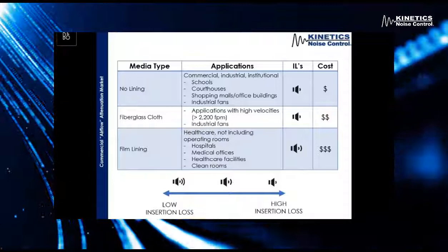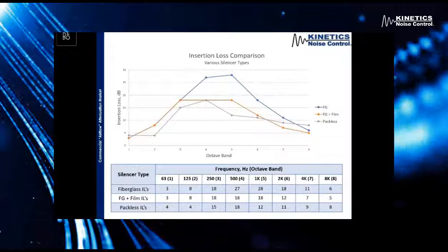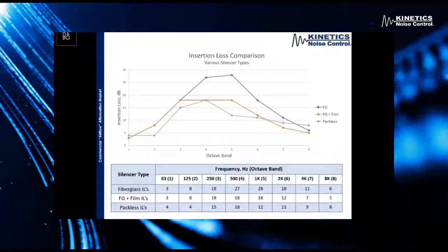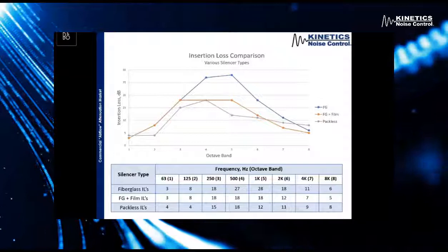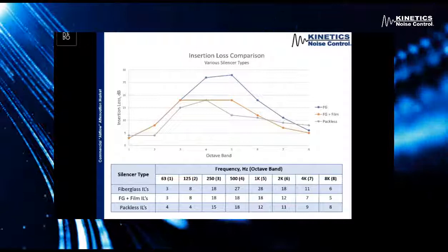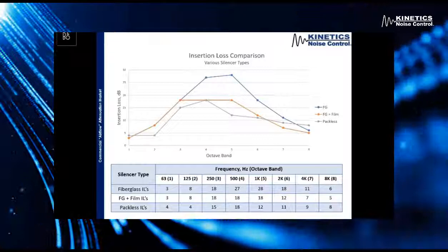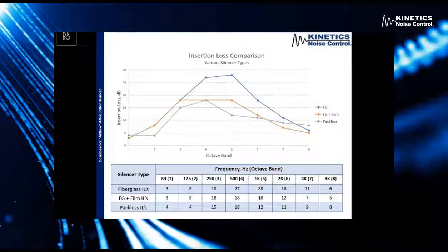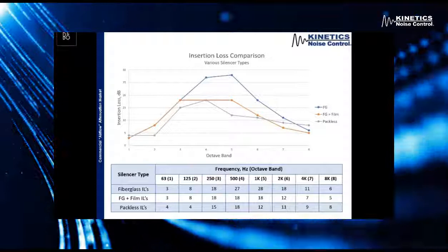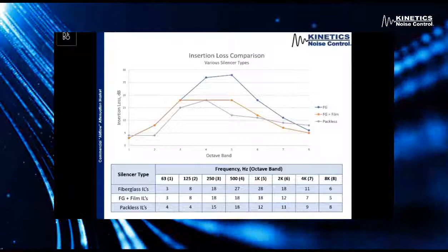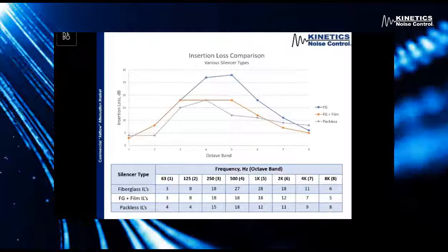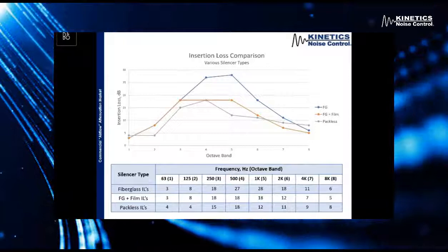To reiterate that further, here we have a graph that shows the difference in insertion loss performance of the three types of silencers. Looking at the blue line — that's a standard fiberglass silencer — you can see that especially through the mid and high frequency bands, we're going to get the best insertion loss performance. As you move to a silencer with a Tedlar or film lining, it degrades performance in the mid to high frequency bands. And as you move to the packless, pretty much through all frequencies, we are going to see a degradation of performance — it's just not going to perform as well. Keeping in mind that these silencers are reserved for very specific applications, we don't want to add unnecessary costs to a project by adding these premium products.